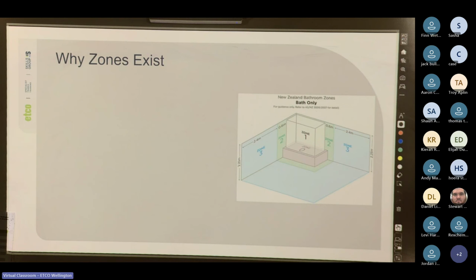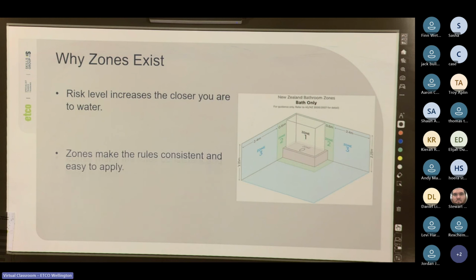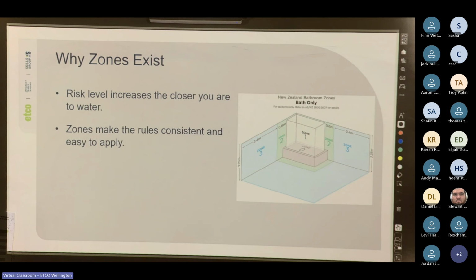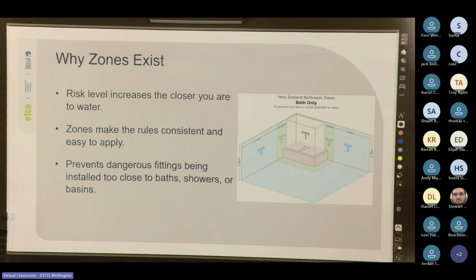Cool. So why do we use the zones? So it stops us from having to do guesswork. It gives us exact boundaries so we can match fittings, IP ratings, and the protective devices. So risk level increases the closer you are to the water, and it makes the rules consistent and easy to apply. And it prevents dangerous fittings being installed too close to baths, showers, or basins.